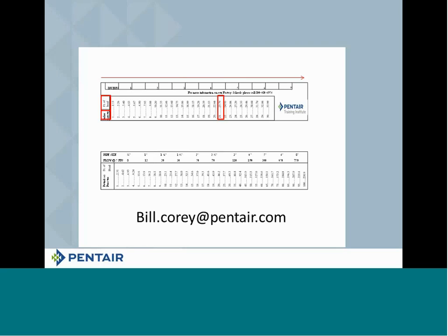There's two things that might cause that to happen. One, of course, is the most obvious, and that is friction loss of the piping system. That's what we were just talking about. Usually that's not the problem. Usually the problem is something is plugging up the suction. If we're pumping out of a lake or something like that, maybe a leaf floating by got pulled into that suction screen, wrapped around the suction screen, and plugged off a whole bunch of holes. And now that pump is working harder.